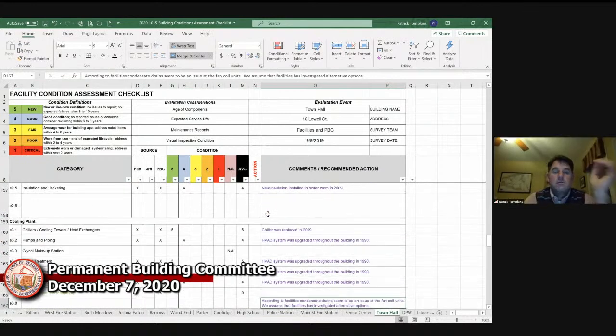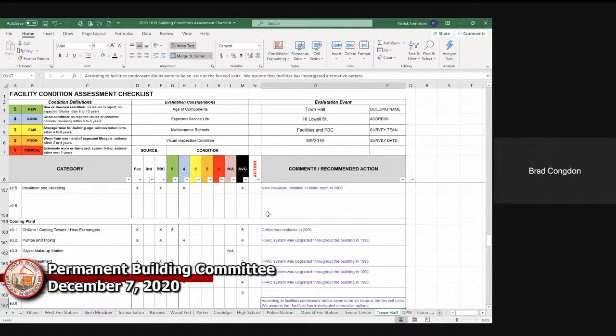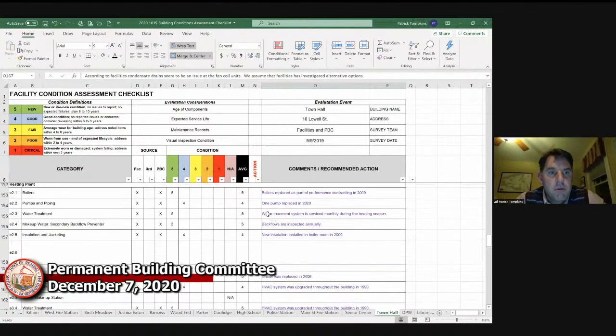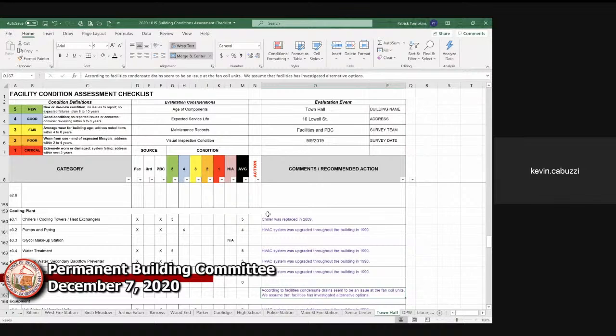All right, cooling plant. Is that all still 1990s vintage? Well, I would say the pumps and piping are, because there are 3 main pumps over there, and they were all definitely from 1990, but we did replace one this year. The one we took out and replaced with a new one, we had it rebuilt and we have it there as a spare for backup. Is that the heating system? Cooling or? Well, there's 3 pumps there, pumps 1 and 2 are for heating, pump 3 is only for the chiller. We only run that during the summertime when we're running the air conditioning.